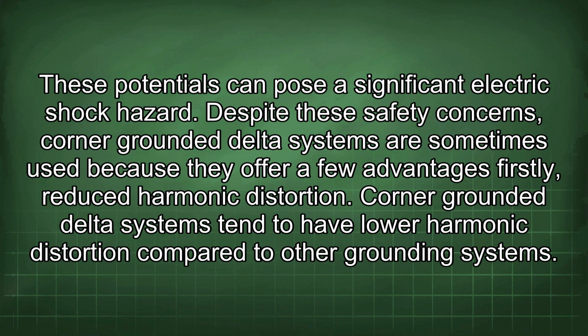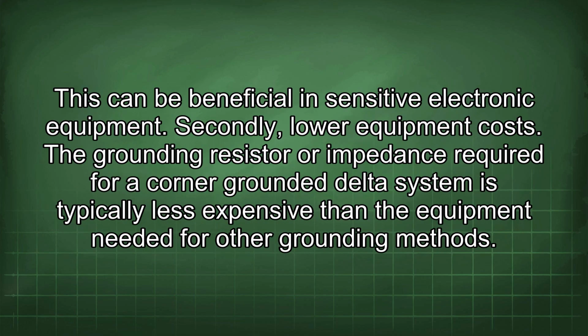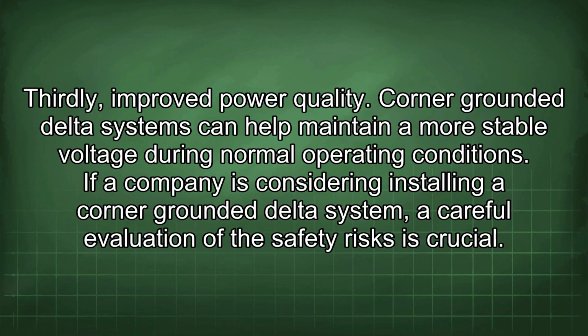Despite these safety concerns, corner-grounded delta systems are sometimes used because they offer a few advantages. Firstly, reduced harmonic distortion. Corner-grounded delta systems tend to have lower harmonic distortion compared to other grounding systems. This can be beneficial in sensitive electronic equipment. Secondly, lower equipment costs. The grounding resistor or impedance required for a corner-grounded delta system is typically less expensive than the equipment needed for other grounding methods. Thirdly, improved power quality. Corner-grounded delta systems can help maintain a more stable voltage during normal operating conditions.